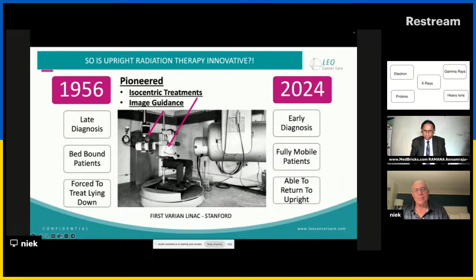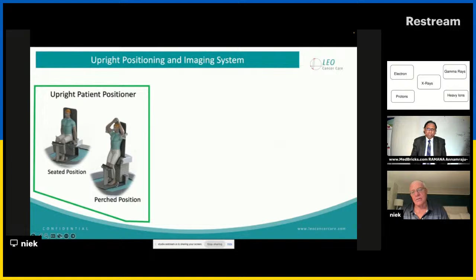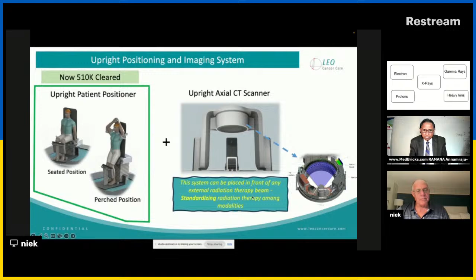Now, what are the benefits of it? Leo Cancer Care developed a positioner that can position the patient seated or semi-standing, and we have a device here that pushes on the knees, and the patient basically sits on the heels, knees, and the bottom. And then we developed a CT scanner that goes around the patient. It's a dual energy CT scanner. And now this machine that positions the patient upright and images the patient upright with a CT scanner can be placed in front of any radiation therapy beam.